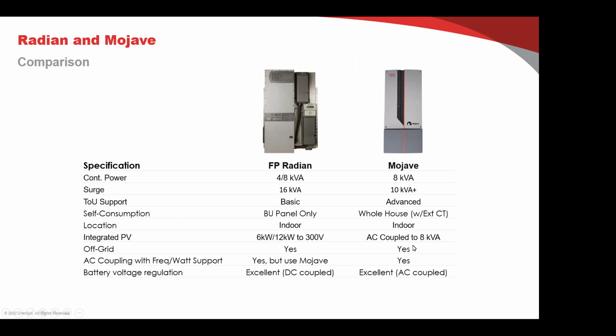With Mojave, I would say no problem. The Mojave regulates the DC voltage so well. I've been testing the Mojave since last August. I've really run through the worst case scenarios like no load, full battery, and it does multi-level charging, so it'll do a complete full absorb cycle. It locks right in within a couple tenths of a volt. It's really, really good. The best I've seen elsewhere, like Radian and some other units, is plus or minus half a volt. Sometimes on a non-SA unit, that's even worse.